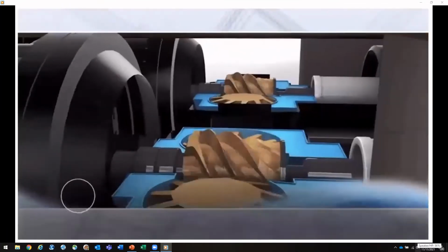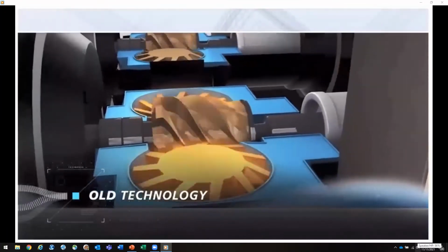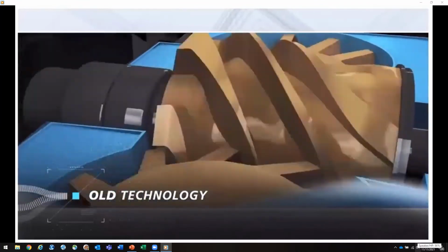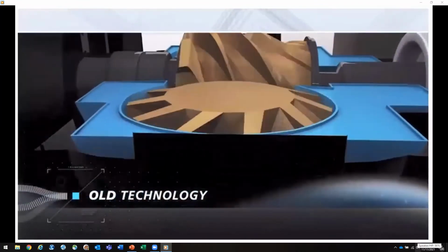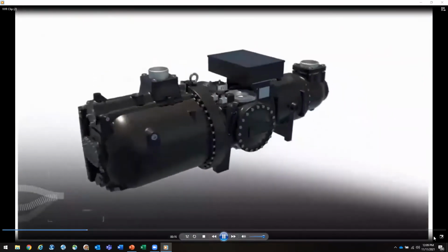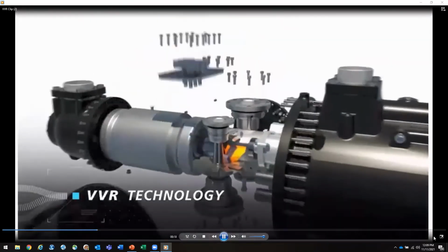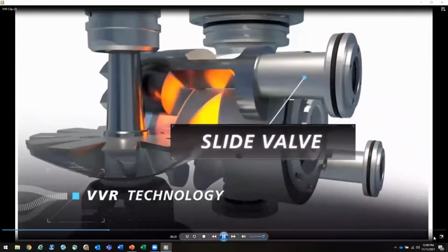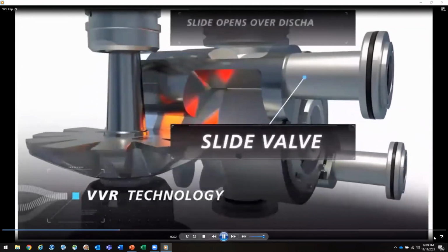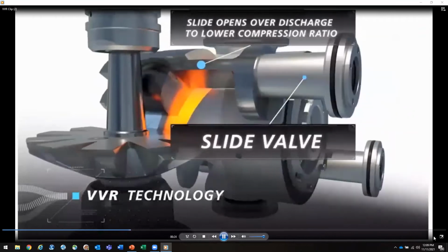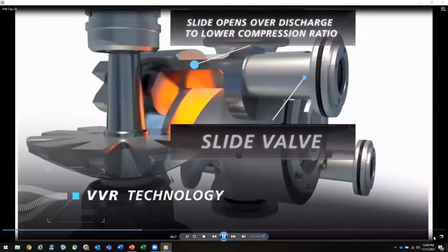In a traditional screw, when gas enters the flute of the screw, it gets compressed along the entire length and is also compressed at a fixed compression ratio. With VVR technology, a slide valve is added to the discharge side of the compressor, allowing us to vary the compression ratio by letting the gas escape sooner before it gets fully compressed.